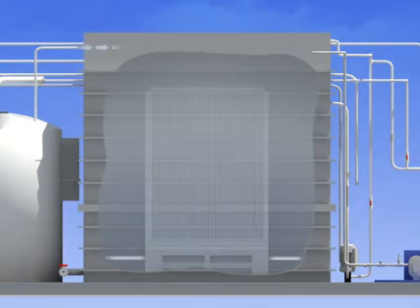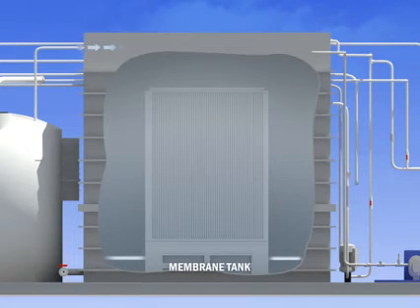While in the membrane chamber, the effluent is filtered through a series of individual membranes. The pore size of the membranes is fine enough that they catch suspended solids, bacteria, parasites, and most viruses. The leftover bugs create a miniature bioreactor in each membrane to digest any organic matter that enters.